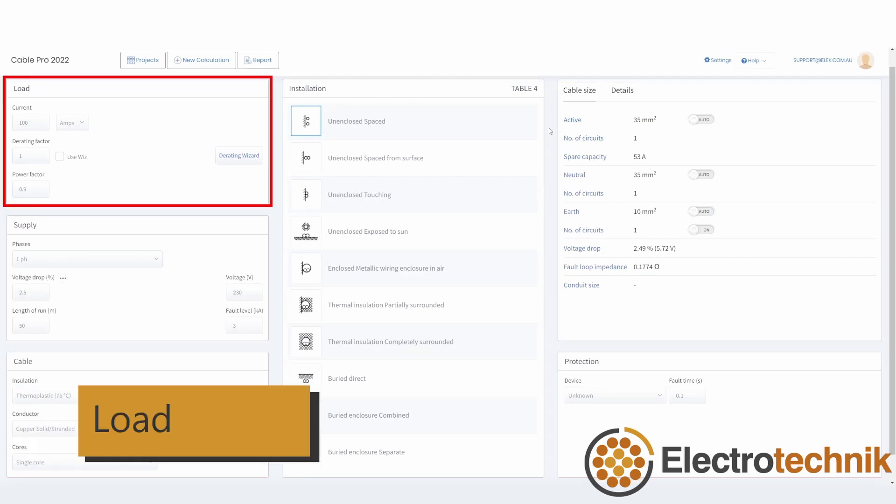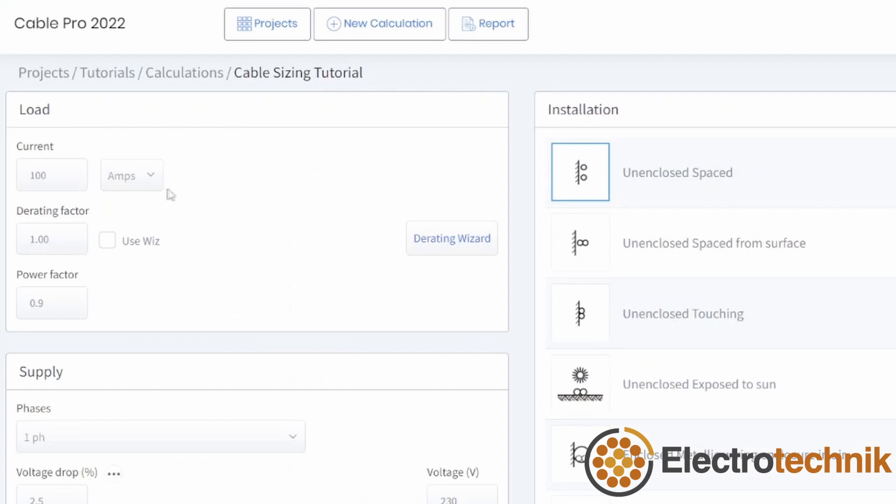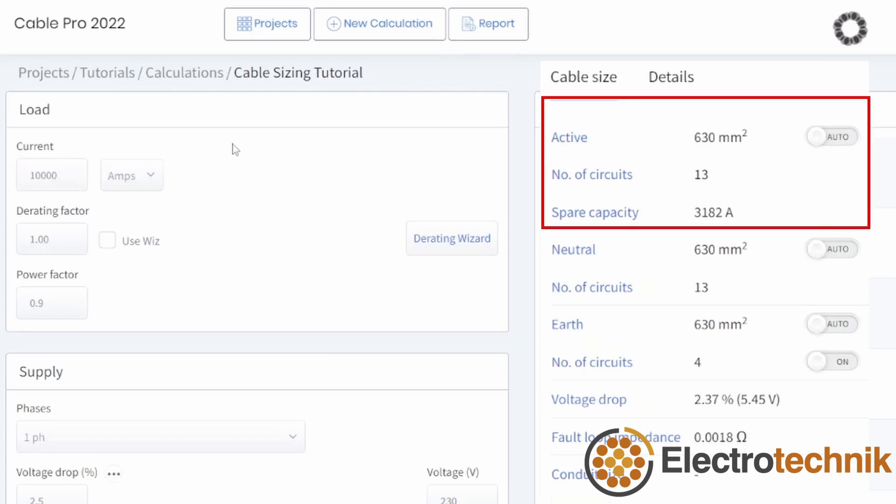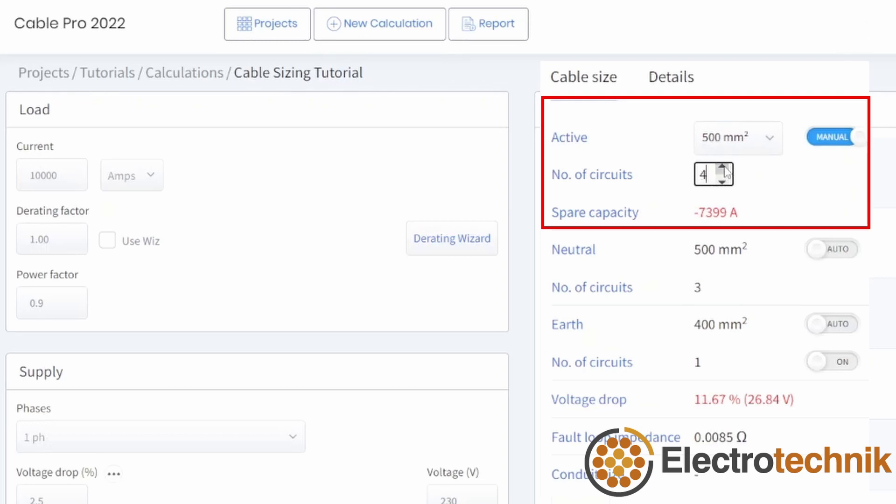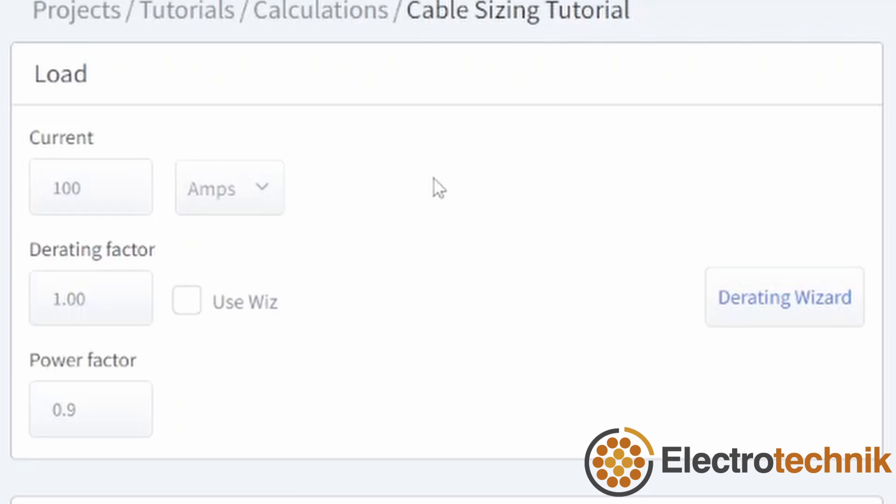Firstly, we'll look at the load section. The load of the equipment is entered as a current, power, or horsepower. You can enter very large loads and the software will automatically calculate the cable size, or you can fix the cable size and number of parallel conductors to check compliance. The load current is used for the minimum current rating of the cable and for determining the actual voltage drop. Power factor of the load is entered here and affects voltage drop. Note that power factor has a big impact on voltage drop for large cable sizes and not so much on small cable sizes.